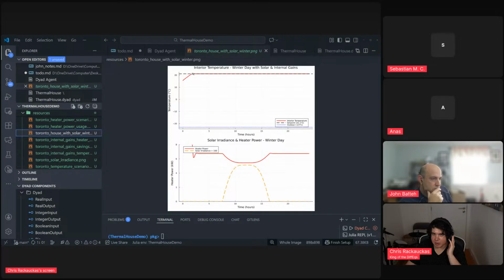Well, I guess this is about the same as before. Now it's just showing it in a much longer time period. But basically it shows us that we're able to hit the set temperature within 2 hours, which is what we thought before, right? And then it's able to keep it pretty effectively there using the PI controller. You're able to use less power during the day, but you're still running your heater during the day. It's just able to go down a little bit.